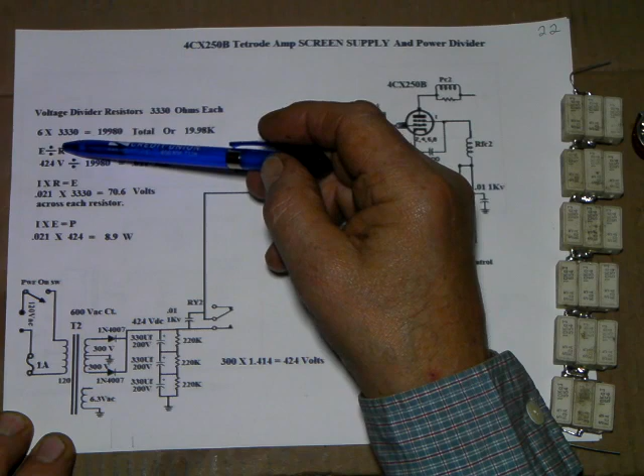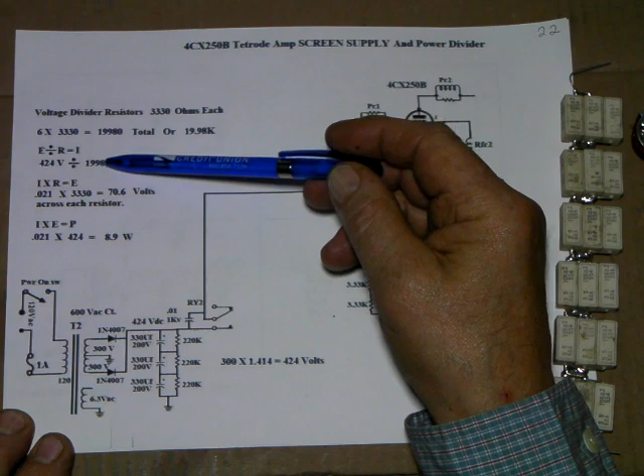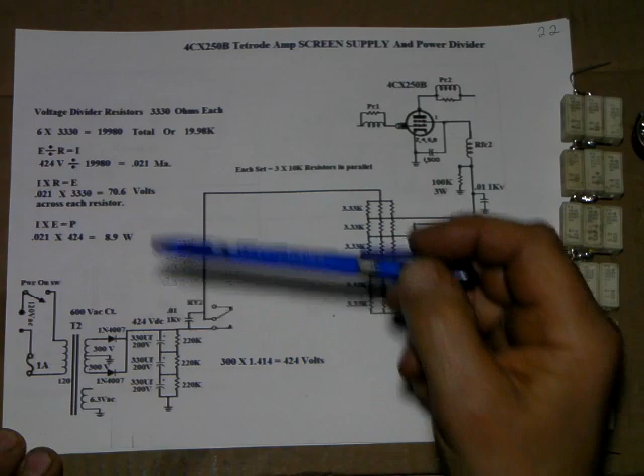Okay, the math behind it: voltage divided by the resistance. Voltage dropped across the resistance gives you a current. So to find that current, it's E divided by R equals current. So 424 volts divided by 19,980 ohms comes out to 0.021 of an amp, or 21 milliamps. So there's 21 milliamps of current being drawn through that.